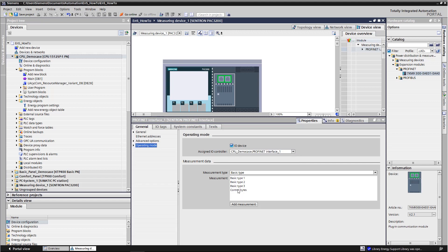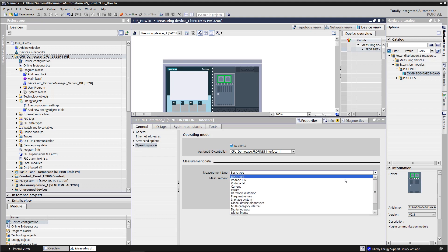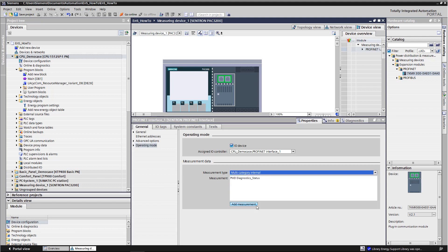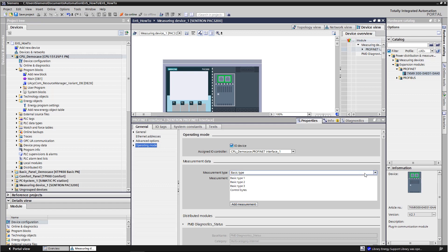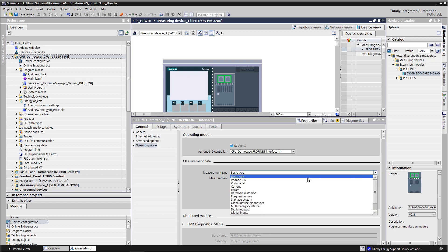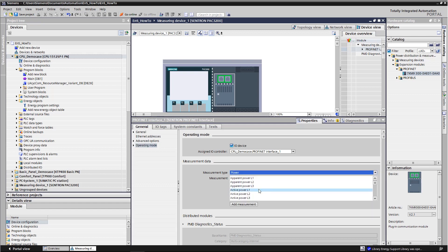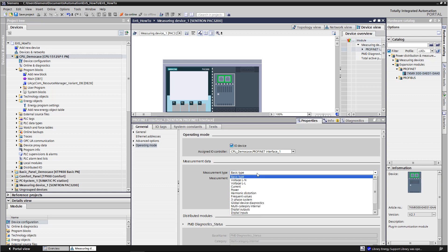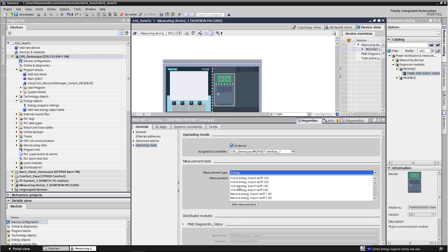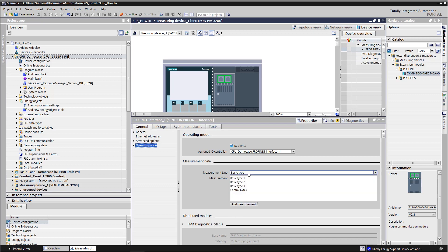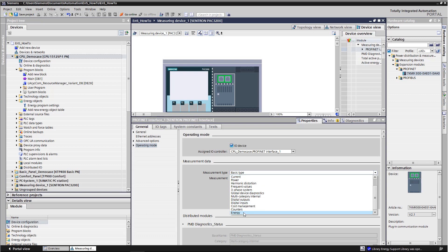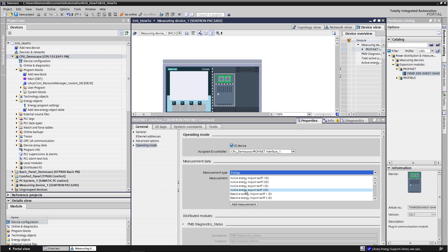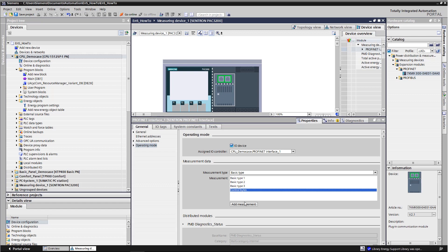As with the energy meter, we have to adjust the I.O. so that Energy Suite can read the basic data. We do this by creating the following parameters: PMD diagnostic status, Total active power, Total active energy import, Total active energy export, and Control bytes.